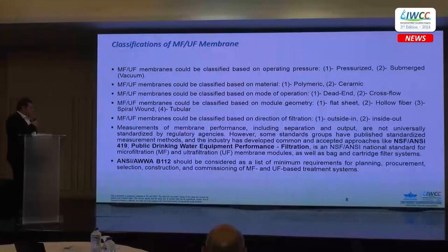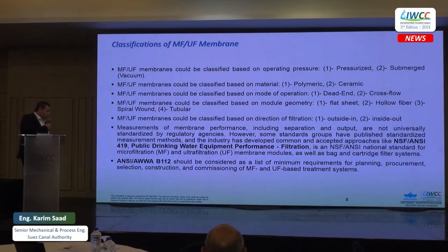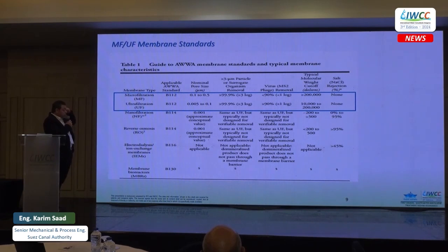And also, AWWA has produced and released the latest edition of the standard AWWA B112 to characterize the minimum requirements of microfiltration and ultrafiltration membranes. We could see here, from AWWA B112, that the nominal pore size for microfiltration ranges from 0.1 to 0.5 micrometer, while ultrafiltration ranges from 5 nano to 0.1 micrometer.